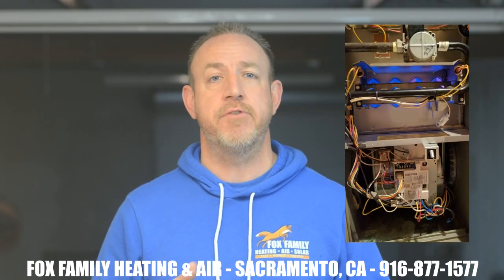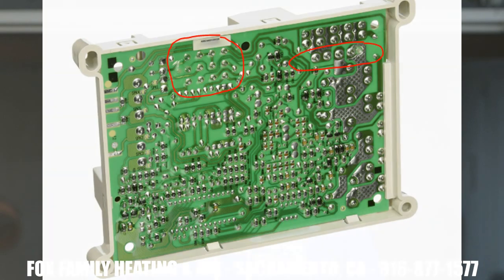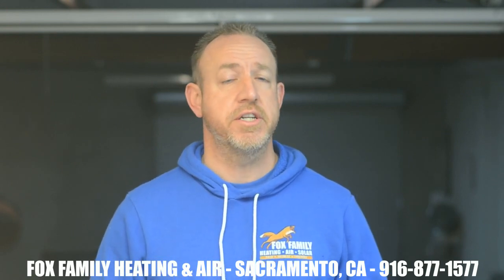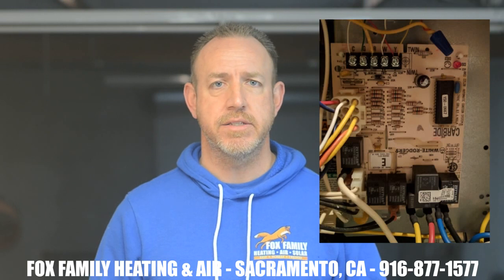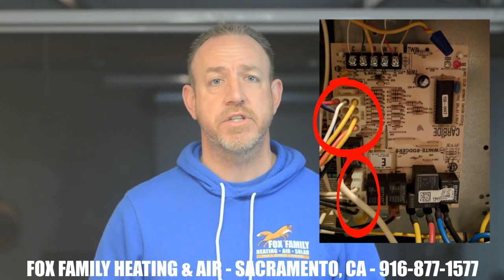That brings me to my first common failure on a control board. I can't tell you how many times I've talked about failed solder connections on the back of a control board. Molex plugs have stems that are secured to the board and soldered in place to adhere to the metallic circuitry that acts like wires do in a house. If the wire has a break in it, that circuit isn't going to work, right? When the backside of those Molex plugs develop a crack, it makes a gap between the stem that goes through the board to the backside where it meets the circuitry. Any fractures in that solder connection are going to start creating intermittent abnormalities. There's a low-voltage Molex plug and a high-voltage plug that's going to be a part of any furnace control that we work on.